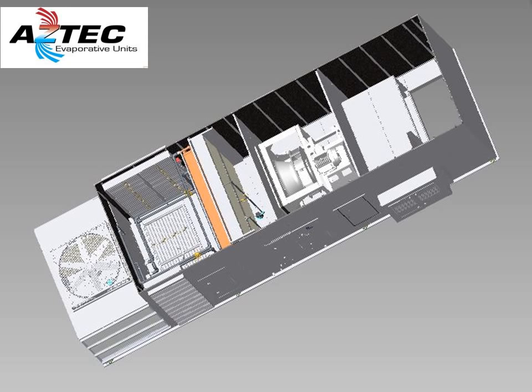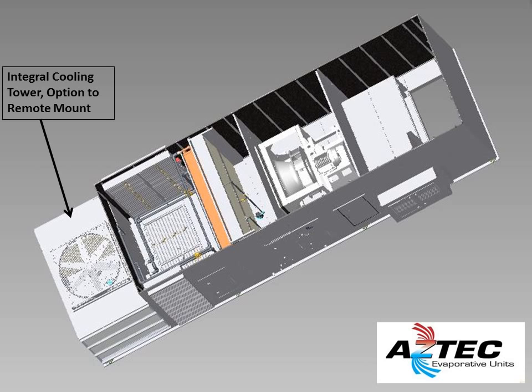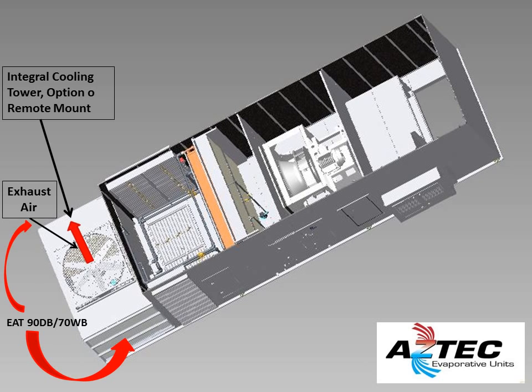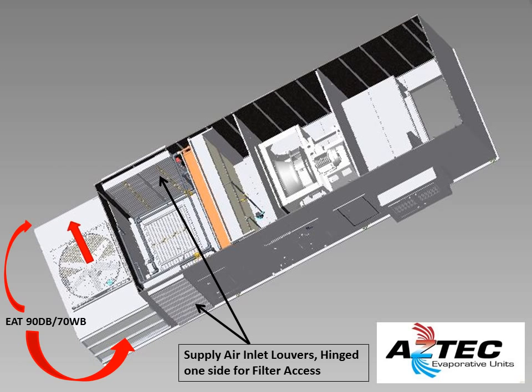This is a top panel cutaway look at our Aztec model ASC-75, an indirect direct evaporative unit. Now let's explore the unit a little further. Here is the stainless steel integral cooling tower. This tower can be packaged with the air handling unit, or it can be set remote, for instance, if you want the air handling unit on the roof and the cooling tower on ground level because you may have a weight limit for your roof. The air enters the tower sides through a 24-inch media and is exhausted through the top. In this case, the entering air temperature is a 90-degree dry bulb and a 70-degree wet bulb.